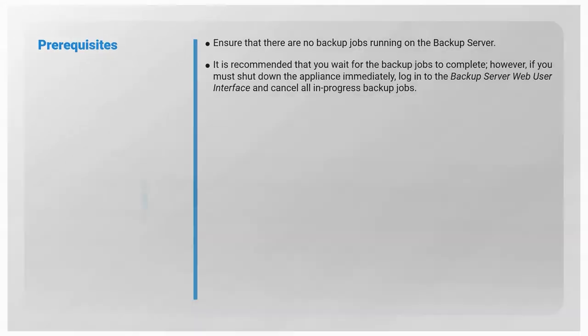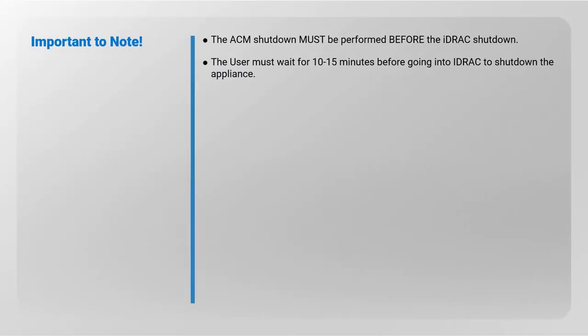Before initiating the shutdown, please review the following prerequisites. It is important to note that the ACM shutdown must be performed before the IDRAC shutdown. The user must wait for 10 to 15 minutes before going into IDRAC to shut down the appliance.